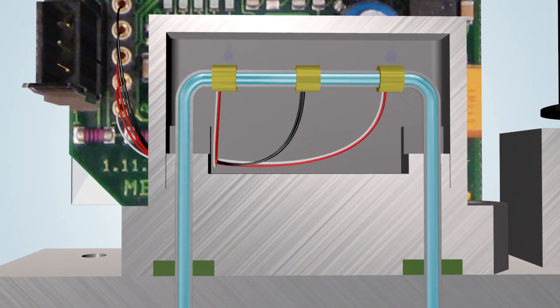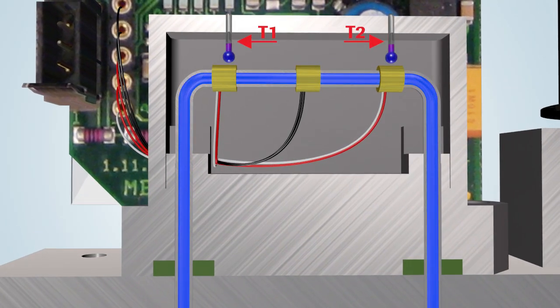The sensor consists of a thin capillary tube fitted with a heater and two temperature recorders. The heater heats the tube. As long as there is no flow, the two temperature sensors heat up evenly. The measured value is zero.